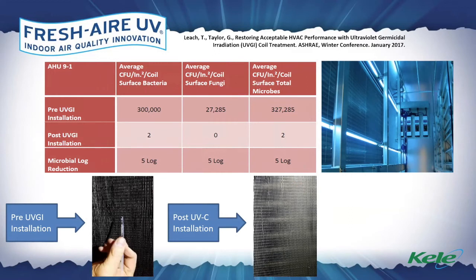This was a pretty foul coil measuring 327,000 CFUs, and that's fungus and bacteria. And they mounted the UV systems. They returned in a couple of weeks for the post-test. And from 327,000 CFUs, it was reduced down to 2. That's a 5-log reduction. That's a 99.999% reduction in microbial load. Microbial load that would have been reintroduced back into the facility along with biologicals and odors.